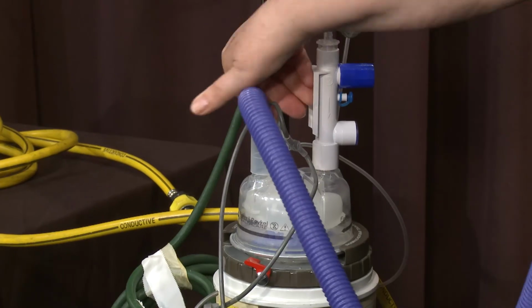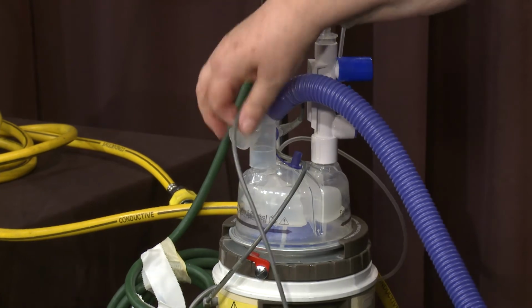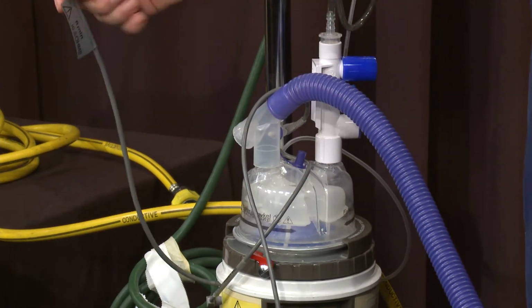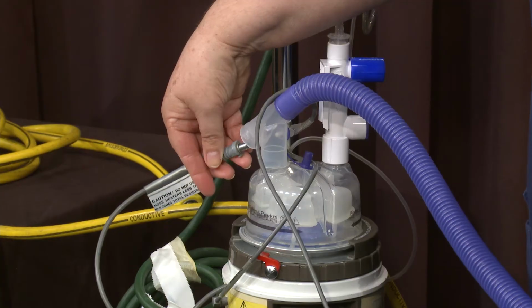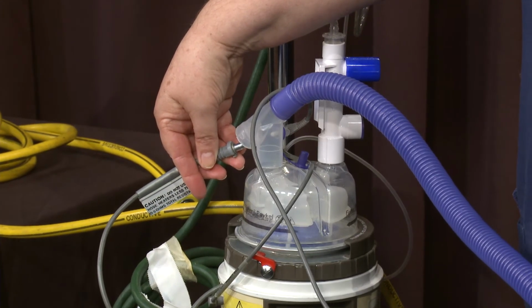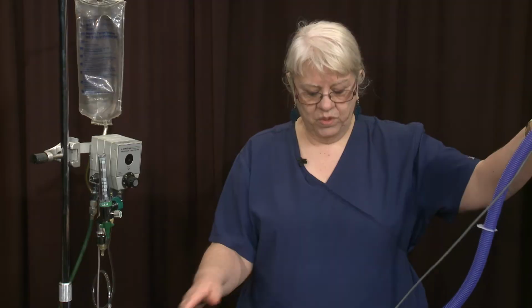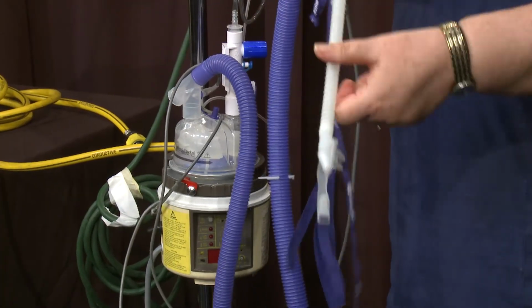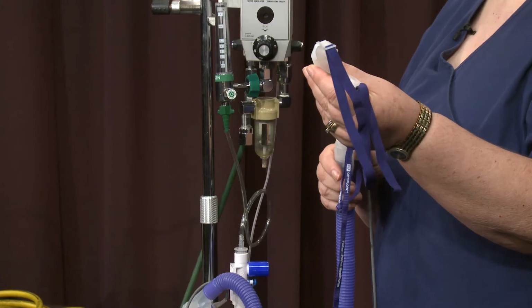So that's one wiring. The second set of wiring goes in the back here of the inspiratory side, and this is hooked up to something like this, a pigtail, which goes in here, and this heats the wires which are insulated and inside the circuit. We know that heated wires are designed to prevent rainout, so that we don't have water sloshing back and forth in the tubing, which would then decrease the flow to the patient. So we have a servo loop and we have the heated wires. Finally, up here at the patient, we have an appropriate size device. This is an adult nasal cannula which can be put on the patient easily, and the patient can eat and drink while wearing this.